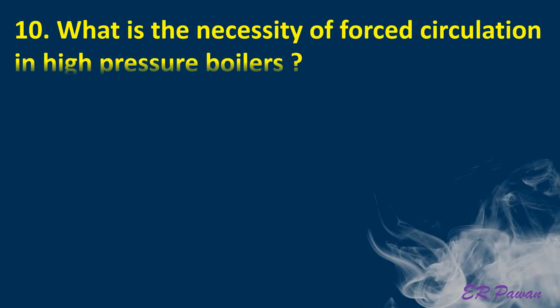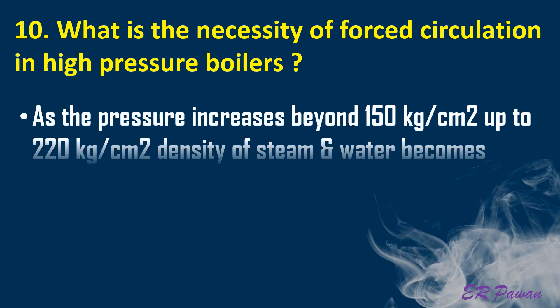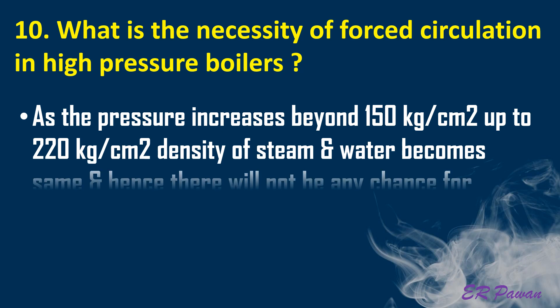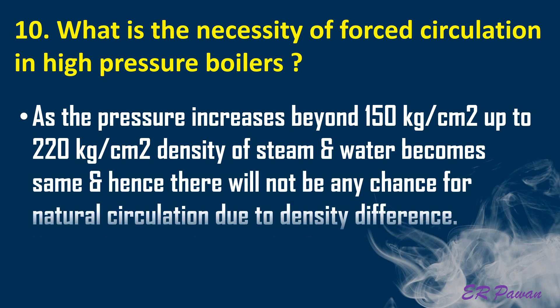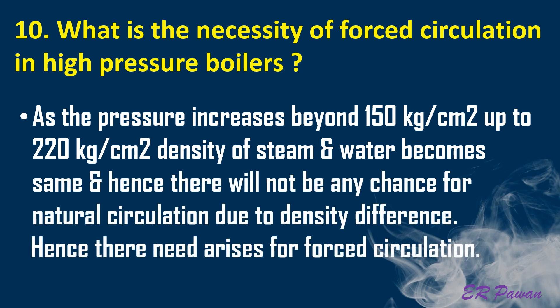Question 10: What is the necessity of forced circulation in high pressure boilers? As the pressure increases beyond 150 kg/cm² up to 220 kg/cm², the density of steam and water become the same, and hence there is no chance for natural circulation due to density difference. Therefore, forced circulation becomes necessary.